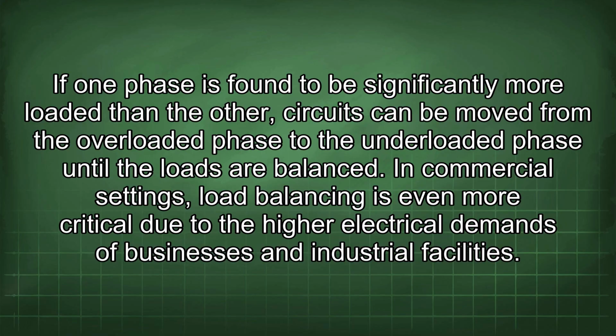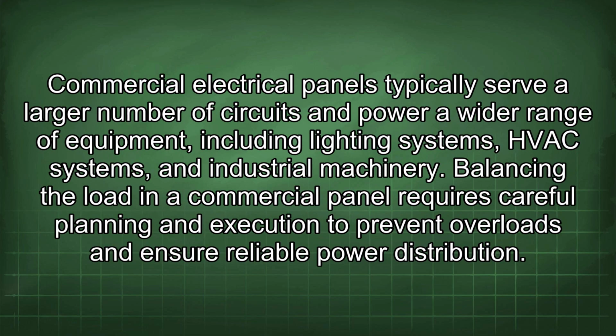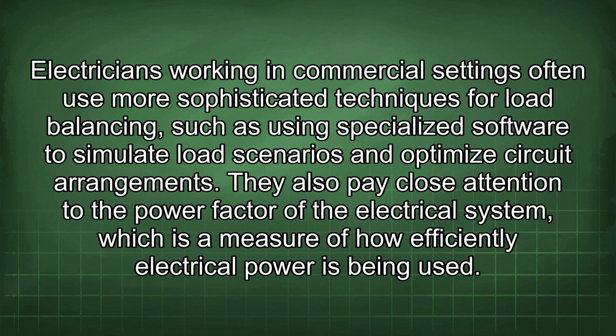In commercial settings, load balancing is even more critical due to the higher electrical demands of businesses and industrial facilities. Commercial electrical panels typically serve a larger number of circuits and power a wider range of equipment, including lighting systems, HVAC systems, and industrial machinery. Balancing the load in a commercial panel requires careful planning and execution to prevent overloads and ensure reliable power distribution. Electricians working in commercial settings often use more sophisticated techniques for load balancing, such as using specialized software to simulate load scenarios and optimize circuit arrangements.